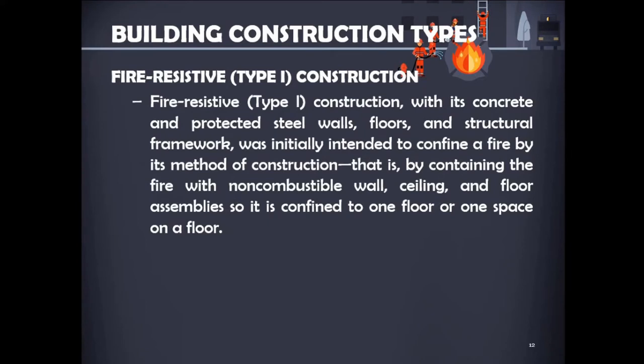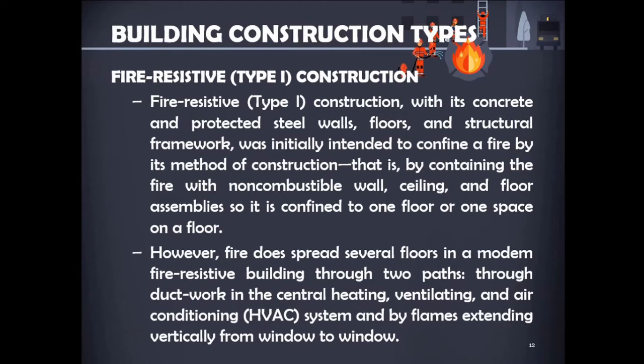Building Construction Types: There are five fundamental categories of building construction. First is fire-resistive Type 1 construction, with its concrete and protected steel walls, floors, and structural framework, initially intended to confine a fire by containing it with non-combustible wall, ceiling, and floor assemblies so it is confined to one floor or one space. However, fire does spread in a modern fire-resistive building through two paths: first, ductwork in the central HVAC system, and second, flames extending vertically from window to window. Air ducts go through walls, floors, partitions, and ceilings, penetrating fire barriers. Fire or hot gases near a return air duct will be sucked into the duct system and blown throughout the structure if the system continues to operate. Therefore, the first action in a burning fire-resistive building should be to shut down the HVAC air system.